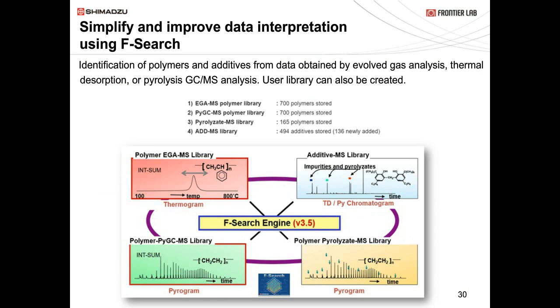F-Search is a library for additives, EGA, and polymers that we recommend using in conjunction with your MS library. A powerful feature is the ability to build your own user library—run your standards, save them, and create your own in-house library for failure and contamination analysis on your samples. The polymer EGA library and polymer PyGCMS library are integrated whole-chromatogram libraries, while the additive MS library and polymer pyrolyzate MS library allow individual peak-by-peak integration.